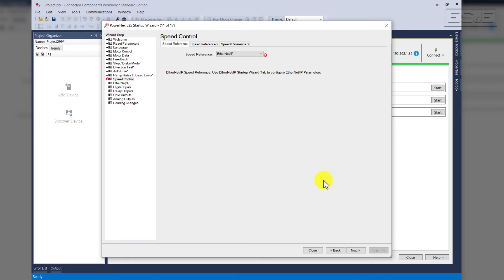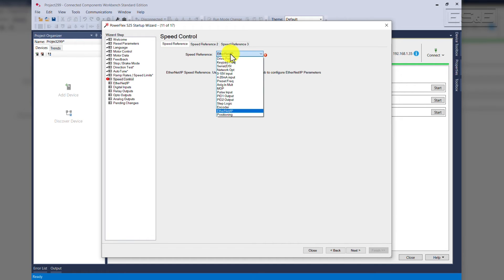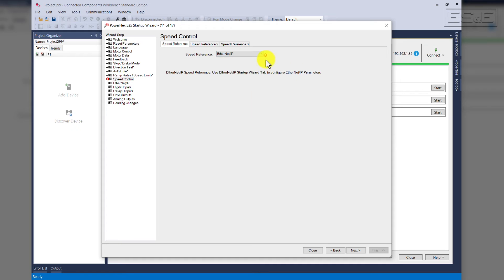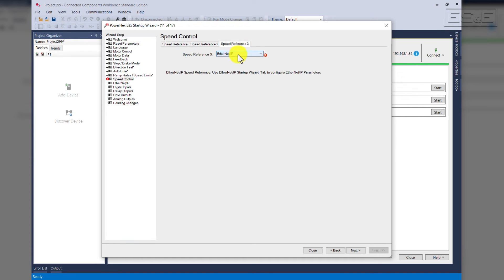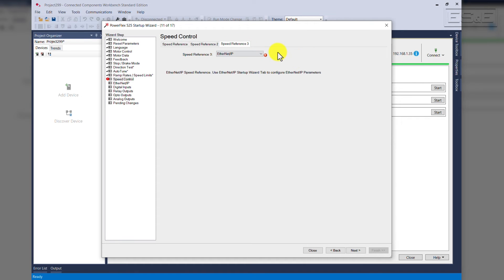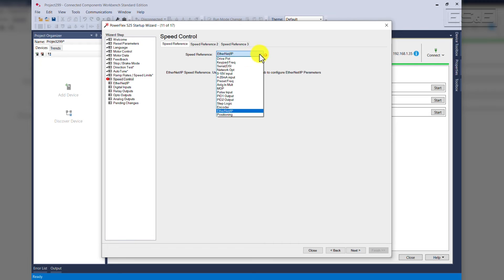At this point, we're going to select Speed Control. Where do we get our command from? The speed reference, we're going to set for zero to ten volts. Please note before I change this, that I got a red error here. That means one of the speed references is set for the same thing. Speed reference three is set for Ethernet IP. None of these speed references can be set for the same value. So speed reference, we'll change it to zero to ten volts.